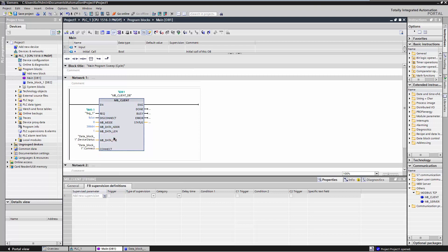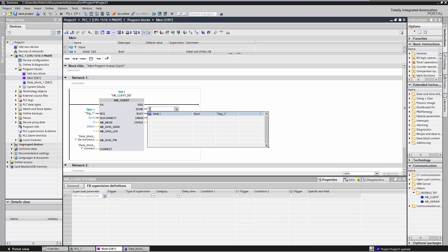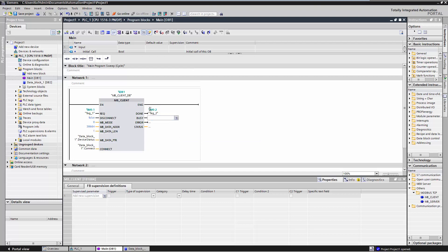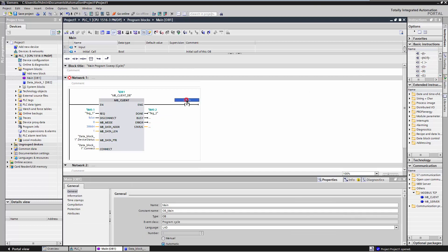Done indicates a successful execution of the instruction. It is set to 1 as soon as the instruction has been executed without errors. To synchronize additional Modbus requests, define a variable for this parameter. Parallel Modbus requests over the same connection are not allowed. To define the remaining output parameters of the MB Client instruction, refer to the documentation for the TIA Portal. Add an instruction to reset the input parameter so that the MB Client instruction is executed only once.